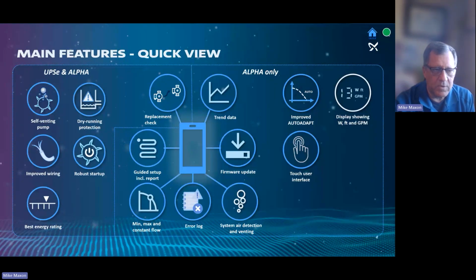Flow set, also with minimum flow and maximum flow. Error log, system air venting, that's separate from the other venting we talked about. This is for the entire heating system that would vent. It's firmware updatable, and trend data. You can connect to the pump after it's been running a while and see how the pump has been running and where it's been running. And we'll look at that later too.